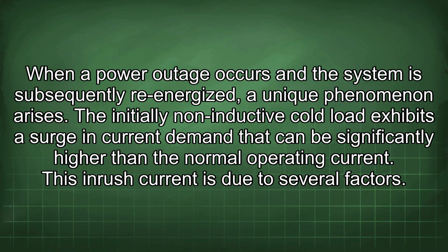When a power outage occurs and the system is subsequently re-energized, a unique phenomenon arises. The initially non-inductive cold load exhibits a surge in current demand that can be significantly higher than the normal operating current. This inrush current is due to several factors.